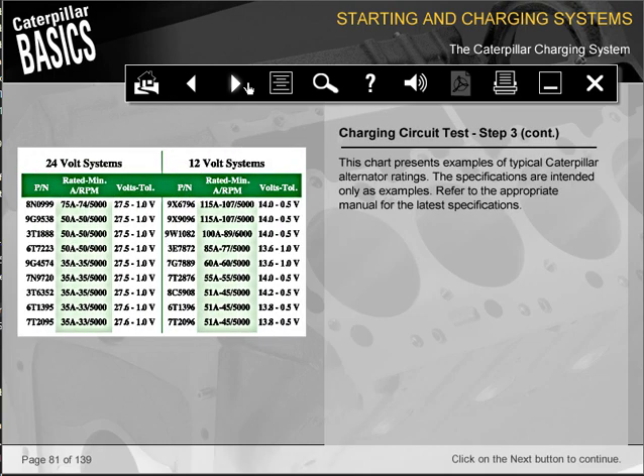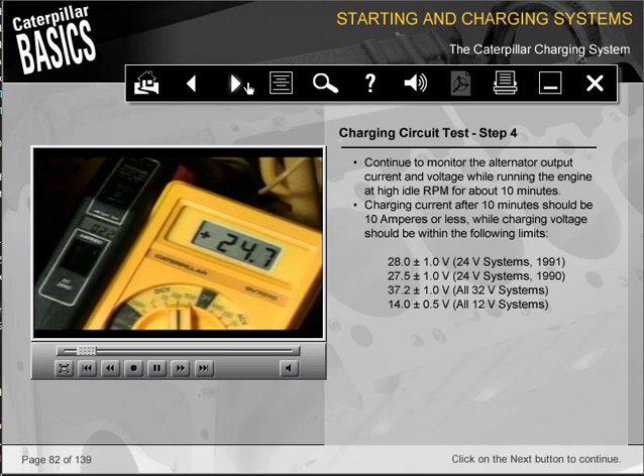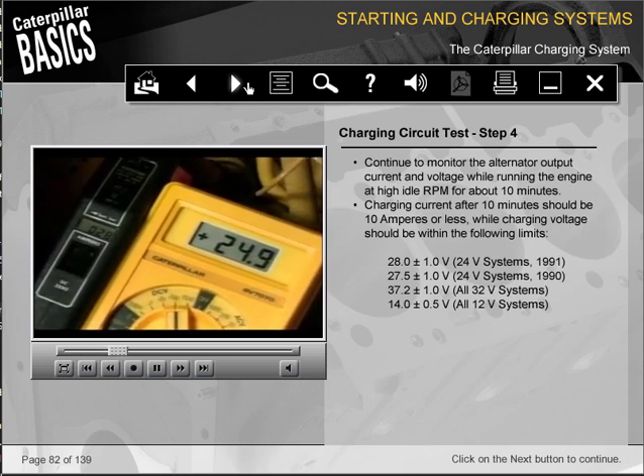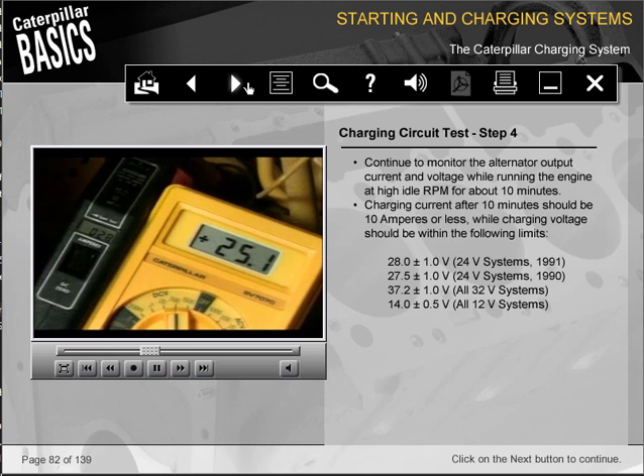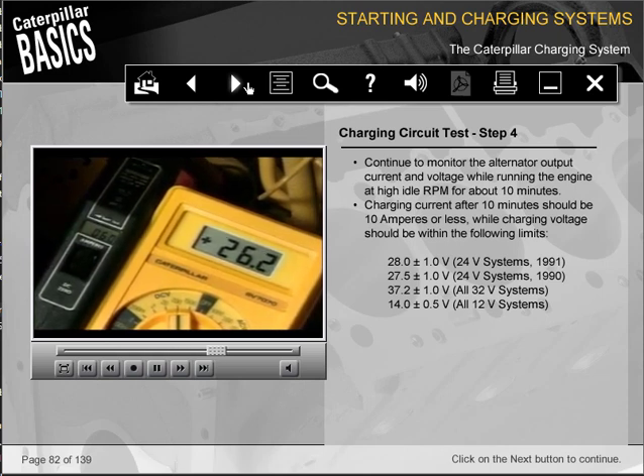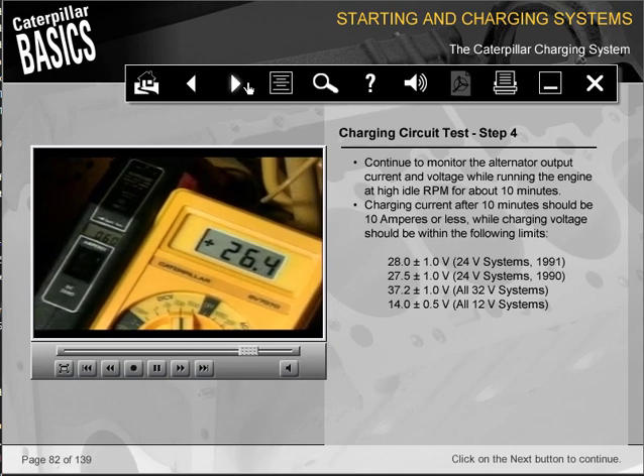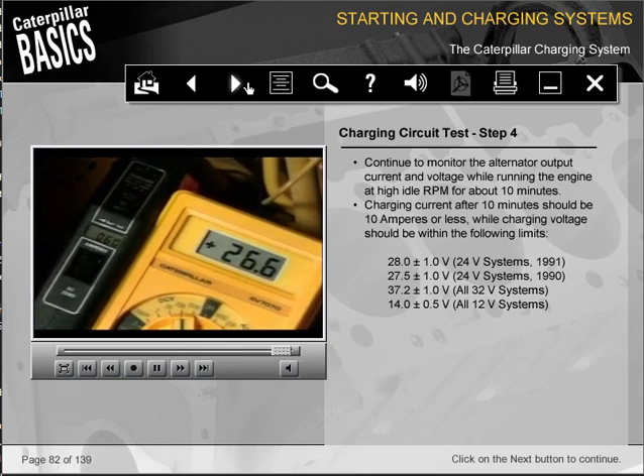This chart presents examples of typical Caterpillar alternator ratings. The specifications are intended only as examples. Refer to the appropriate manual for the latest specifications. Continue to monitor the alternator output current and voltage while running the engine at high idle RPM for about 10 minutes. Charging current after 10 minutes should be 10 amperes or less, while charging voltage should be within the following limits.